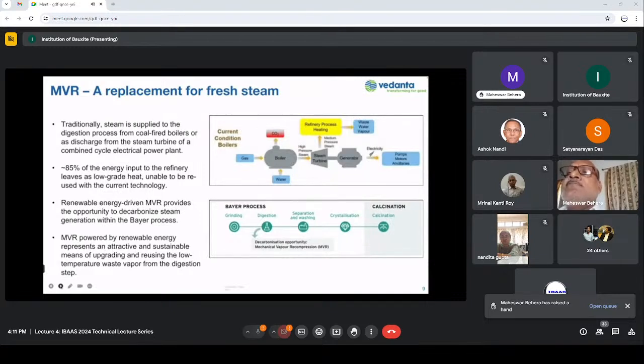Traditionally, steam is supplied to the digestion process from coal-fired boilers or as discharge from the steam turbine of a combined cycle electric power plant. In the case of a low pressure refinery, the high pressure steam is used for electricity generation, and medium to low pressure steam is used for the process heating as a refinery energy input. It has been seen that a significant amount of the energy input of the refinery leaves as low grade heat and is unable to be reused with the existing technology.